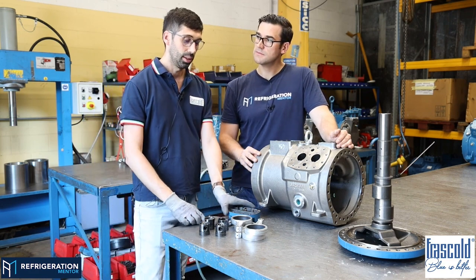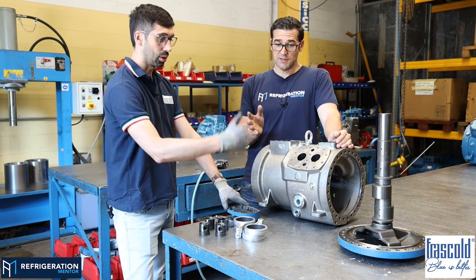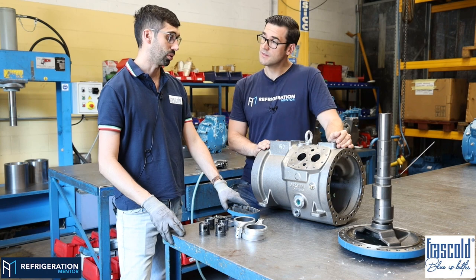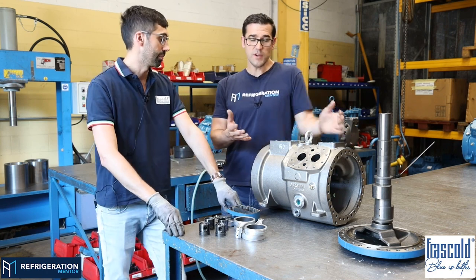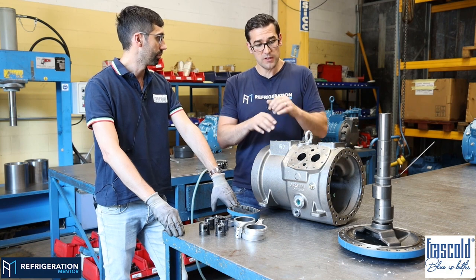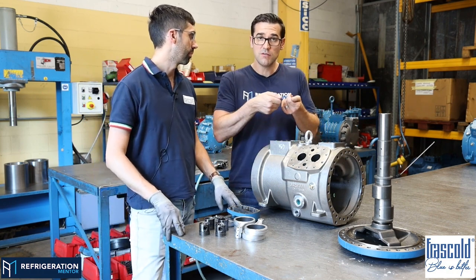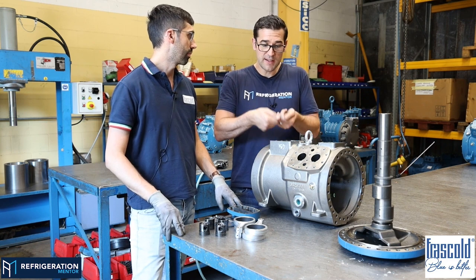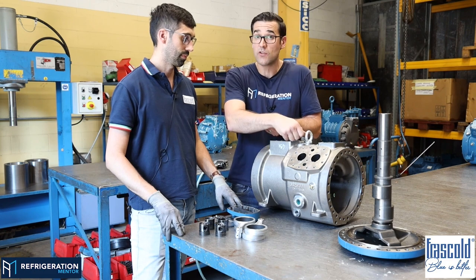It is a real example of what can happen, going backwards to the motor to cause the electrical failure. So what you need to do is take your meter, once again, isolate the compressor, make sure it's off, take your meter and check the resistance. If that is a grounded compressor, you'd be on one of the legs, you put it to the compressor, a grounding point.